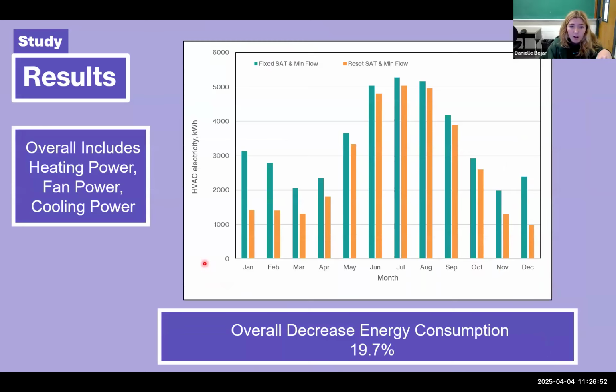Then for the overall HVAC electricity, the energy consumption decreased by 19.7%. So this includes everything: the heating power, fan power, cooling power. So just by manipulating the controls, we were able to decrease our energy consumption by about 20%.